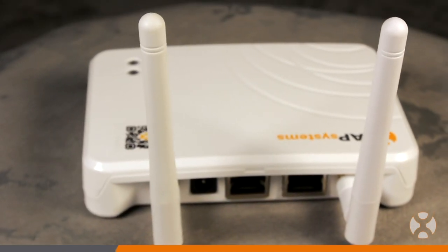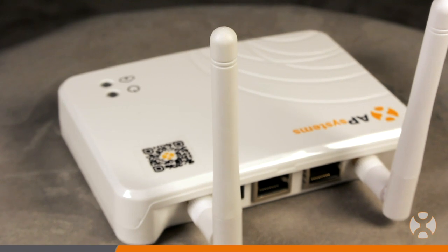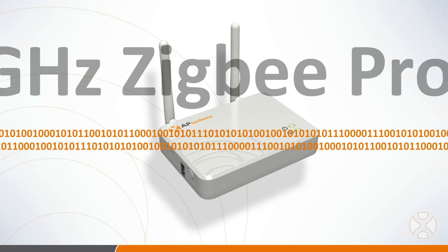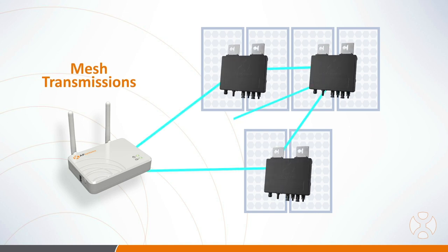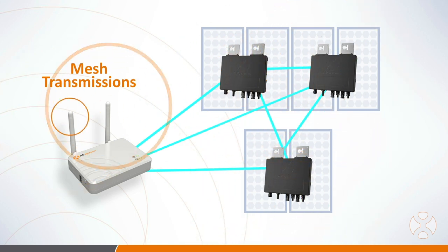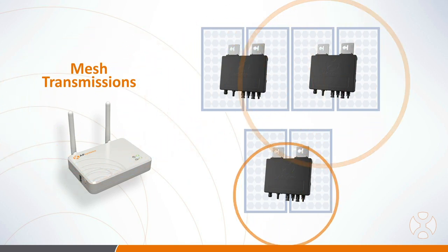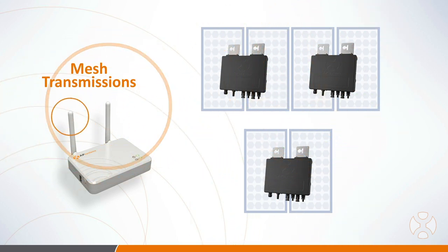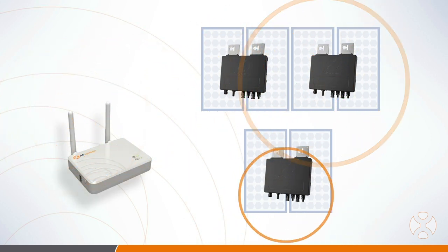A quick note about Zigbee: due to the volume of data points transmitted and collected in today's solar PV systems, many manufacturers have transitioned to high-speed data communication platforms like Zigbee. The ECUR utilizes a 2.4 GHz Zigbee protocol to create a mesh network with its microinverters, allowing microinverters to communicate data not just directly with the ECU, but through other microinverter units. The resulting speed is up to three times faster than power line communication, or PLC.